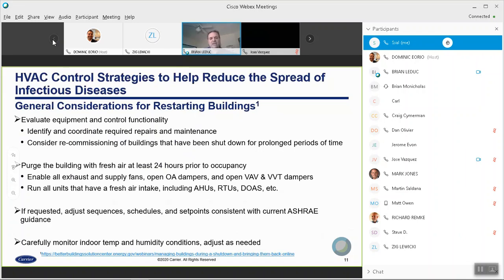So recommissioning, evaluating the current status of all the equipment and controls, is a very important step in terms of reopening. There has been some guidance to suggest a 24-hour ventilation period prior to occupying. So obviously, to achieve that, you'll need to be enabling all of your exhaust and supply fans, opening your dampers, zone dampers, and running all the units that have fresh air intake. If requested, again, as part of a reopening strategy, this would be the time to adjust sequences and schedules to comply with current ASHRAE guidance.